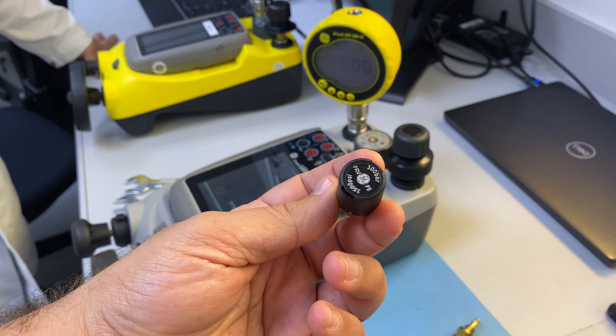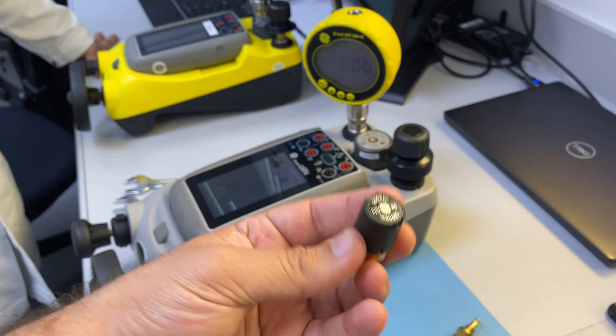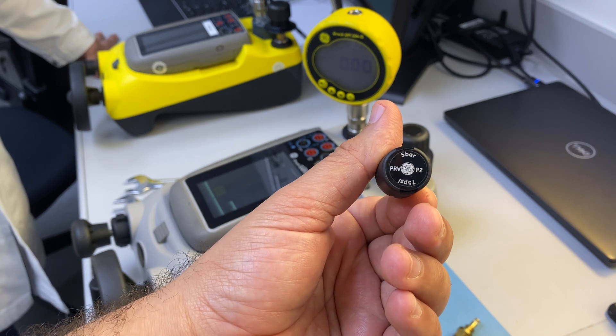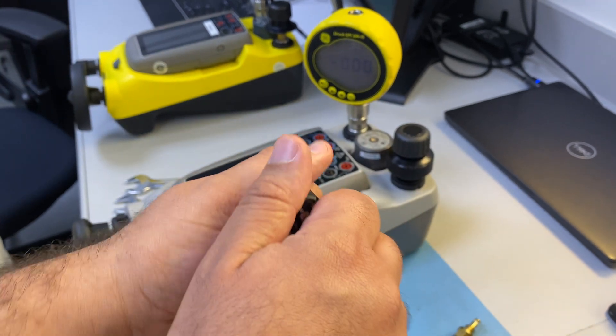In this video we will see how to adjust direct pressure relief valves. All types of pressure valves come with different settings — a factory set and an adjustable range. We will adjust the io620 PRV P2, which has a range of 3 to 7 bar and a factory set of 5 bar.